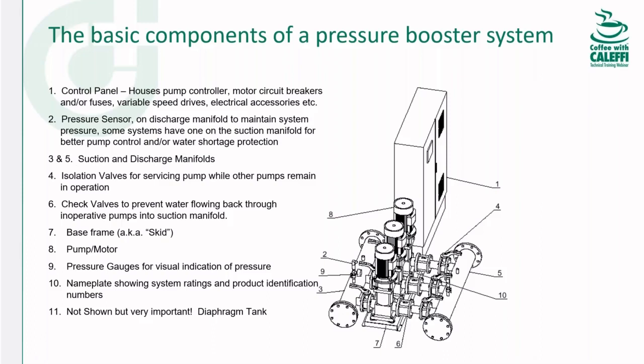Next, we've got suction and discharge manifolds, pretty obvious, but when you're dealing with high-rise pressure boosters, the discharge manifold has to be rated for the maximum possible pressure. What I mean by that is you need to sum up the maximum inlet pressure from the city, and then add to that the max shutoff pressure of the pump. When you look at the pump curve, all the way on the left, the highest boost possible at zero flow, that's what you need to add to the incoming pressure, because a pump might accidentally be running at 100% speed. It's going to be boosting that much pressure. So if you've got 100 PSI coming in and the pumps are designed for 180 PSI, but they can actually do 200 PSI, that's 300 PSI sitting on the manifold. Check valves. You can't forget the check valves.